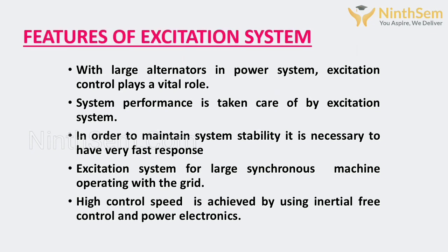Features of the excitation system. With large alternators in the power system, excitation control plays a vital role. System performance is taken care of by the excitation system. In order to maintain system stability, it is necessary to have very fast response from the excitation system of large synchronous machines operating with the grid. High control speed is achieved by using inertia-free control and power electronics.